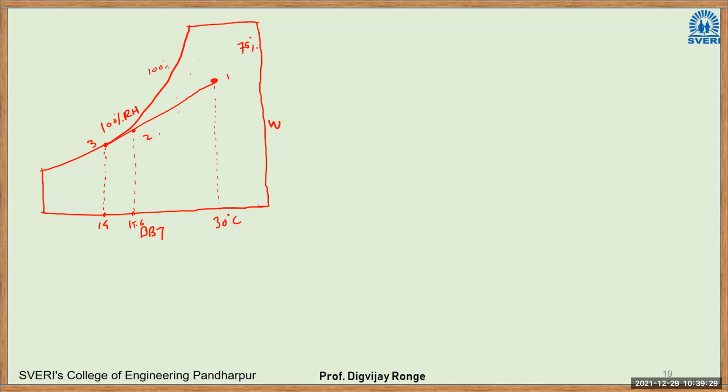The very interesting thing here is, when you take the segment ratio, let us say this is a complete segment, this is X1 and this is X2. When you take the ratio X2 divided by (X1 plus X2), it will be 0.1. That is the bypass factor. So this is the meaning of the bypass factor here.